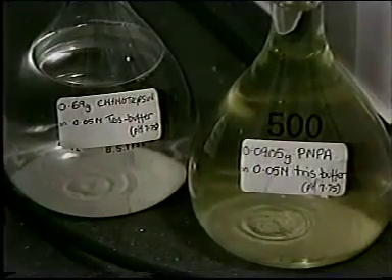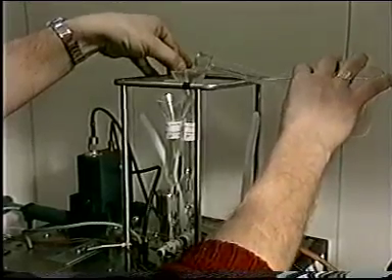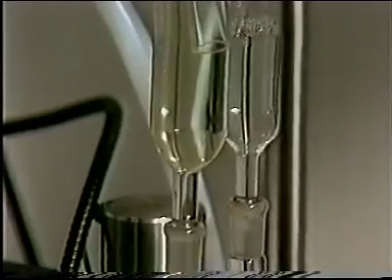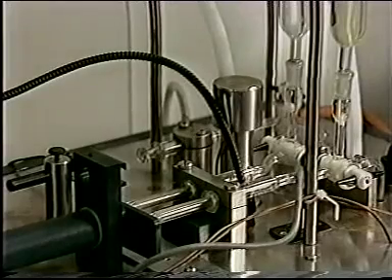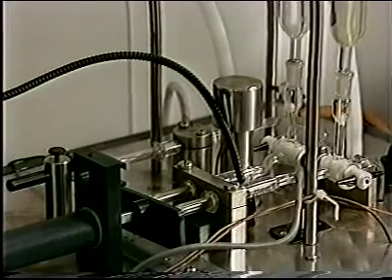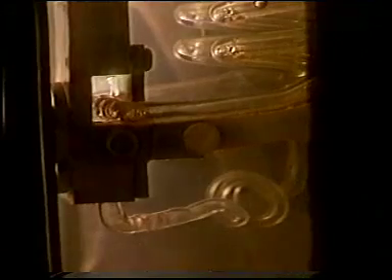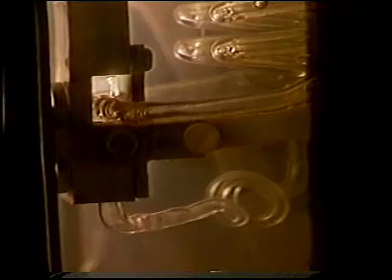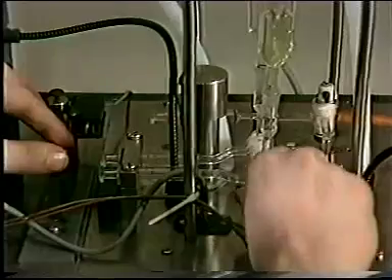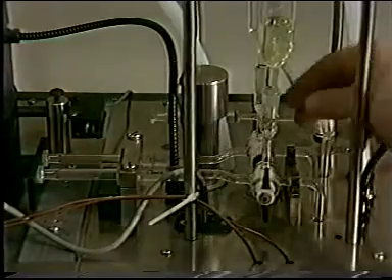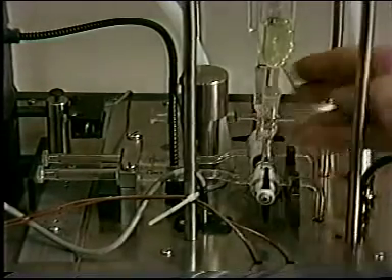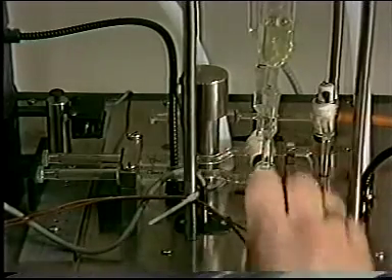The paranitrophenyl acetate and the chymotrypsin solutions are charged into two reservoirs which feed two ram-driven syringes. When these are compressed, they will express equal volumes of each solution into a mixing chamber, which allows efficient mixing of the reactants in a fraction of a millisecond. As I purge bubbles from the system, you can get some impression of how the mixing takes place.